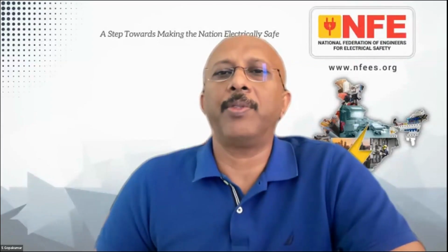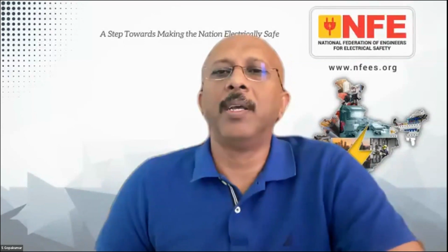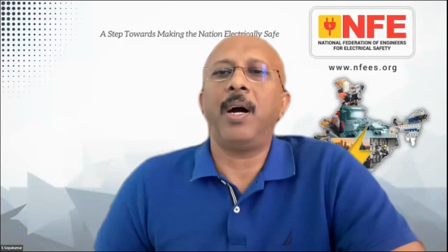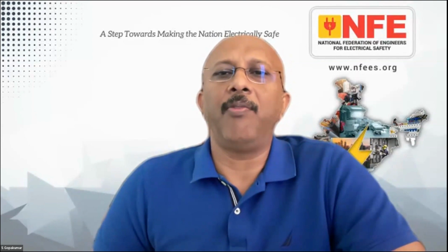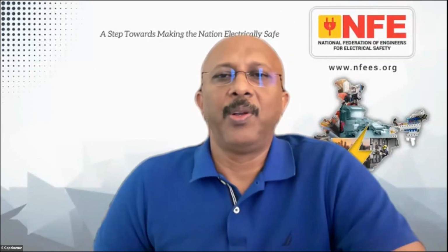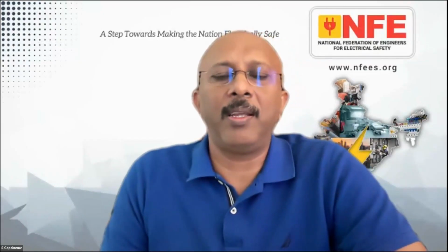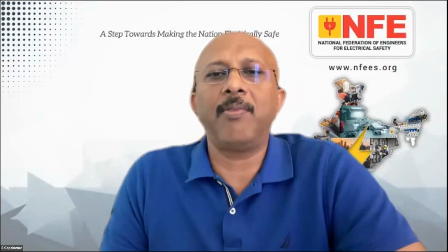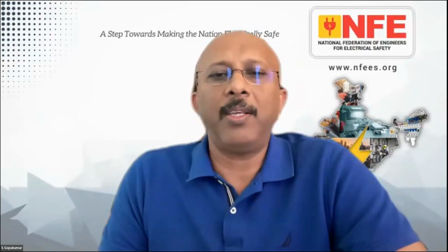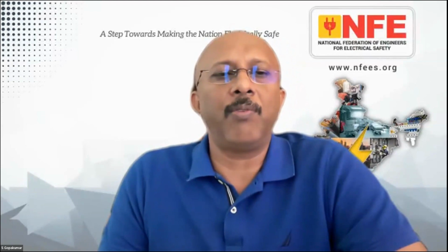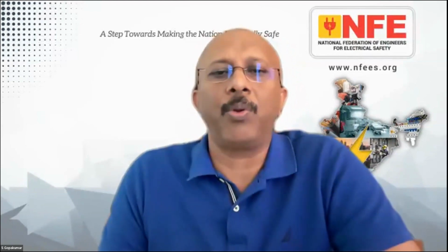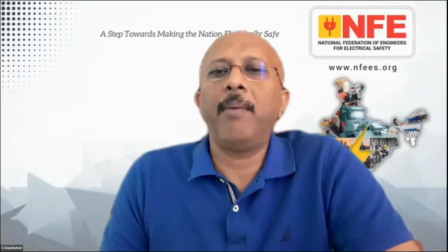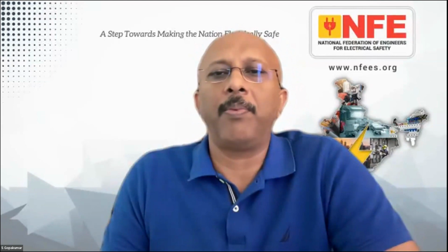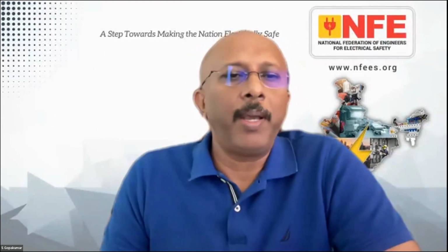Thank you very much. Now we have a question from Mr. Krishnendu. In the Indian context, we also have a low voltage situation. How does this impact fault loop impedance? Of course, Mr. Krishnendu, voltage is an influencing factor. If you look at the formula, if the voltage is less, the impedance doesn't change, but the fault current is less. Once the fault current is less, of course, the disconnection time is more. So a big voltage drop in the circuit means the system may not work. The fuses may not trip. You have to be careful. I hope my answer is clear, Mr. Peter.